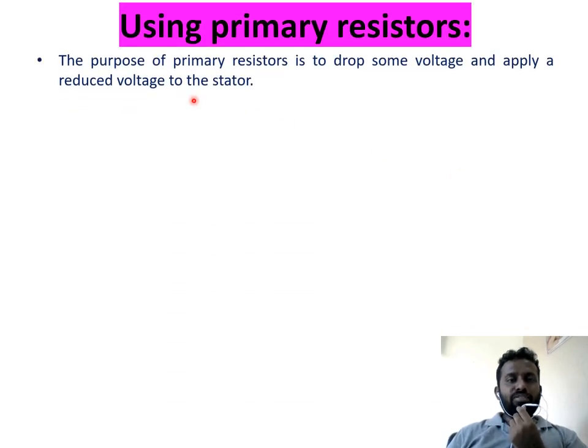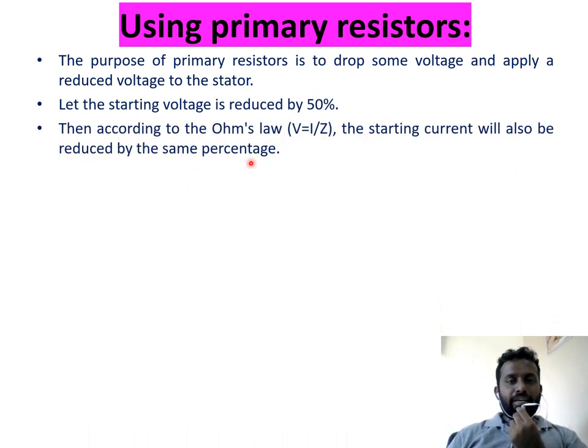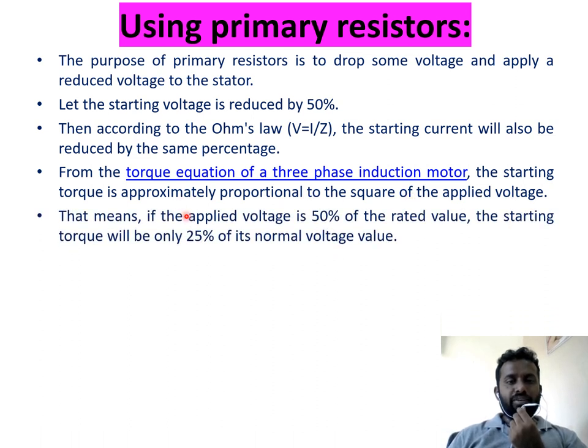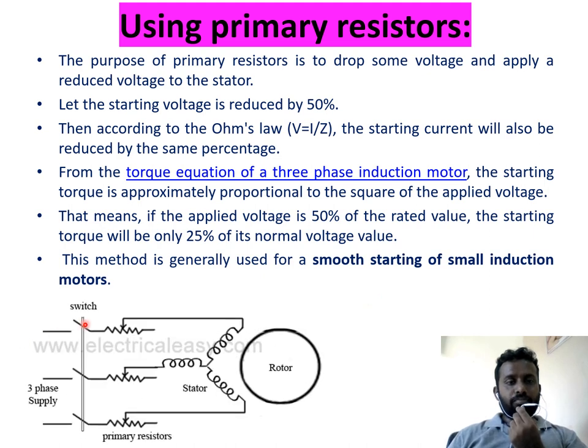Primary Resistance Starter: the purpose of primary resistors is to drop some voltage and apply a reduced voltage to the stator. If voltage is reduced, current reduces. If starting voltage is reduced by 50 percent, according to Ohm's law, starting current will also be reduced by the same percentage. From the torque equation, starting torque is approximately proportional to the square of the applied voltage. So if voltage is 50 percent of rated value, starting torque will be only 25 percent of its normal value. This method is generally used for smooth starting of small induction motors.